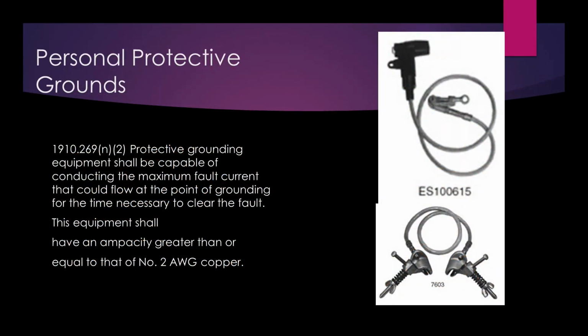When it comes to grounds, the big thing is make sure they cannot be smaller than number 2 AWG, that American wire gauge thing. So it cannot be smaller than number 2, which means a piece of number 6 soft drawn or hard drawn with a couple hotline clamps ain't a ground. That ain't a ground. If that's all you've got in a pickle, that's all you've got in a pickle, but that's not considered a ground out there.